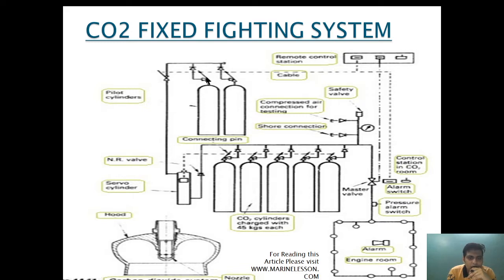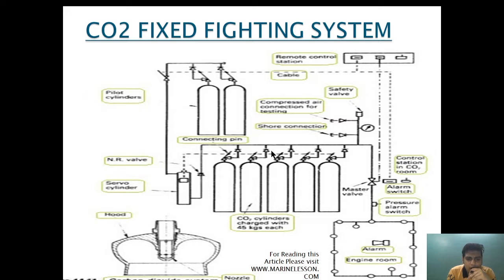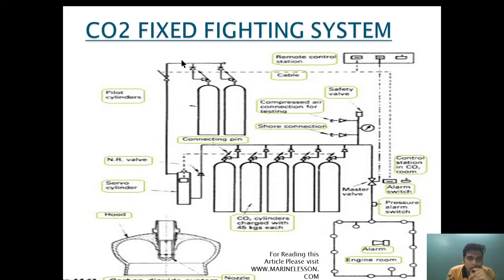As soon as the pilot cylinder door is open, the alarm will go on, the fan circuit will be deactivated, and the fan will go off. Alarm will be activated indicating the release door has been opened. After that, through the remote control station this valve is opened, and the CO2 from the pilot cylinder will go and come to the servo cylinder. This servo cylinder is connected through a wire mechanism to the connecting pin of the individual CO2 bottle.